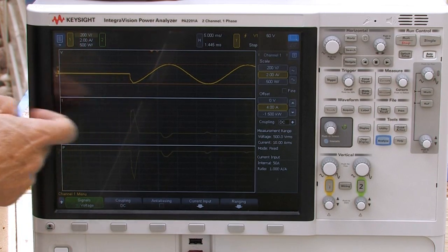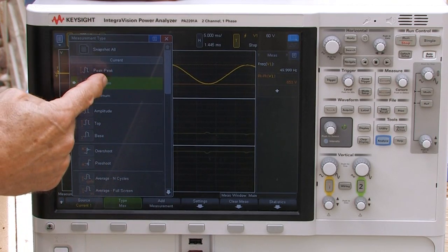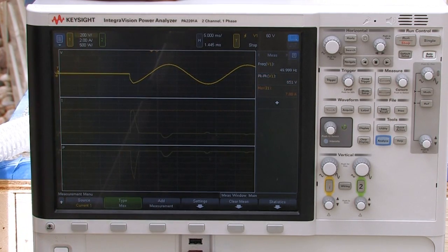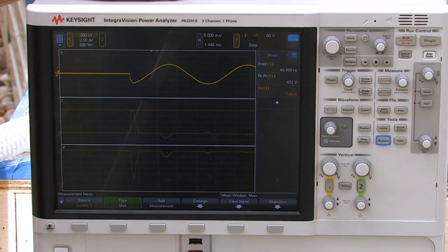What I would like to do is see what that maximum value is. So I'm going to use the measurement function on the oscilloscope. So click measure and go ahead and add a measurement and we'll use the maximum. So you can see the line drawn there and it got 7.88 amps maximum on that inrush.